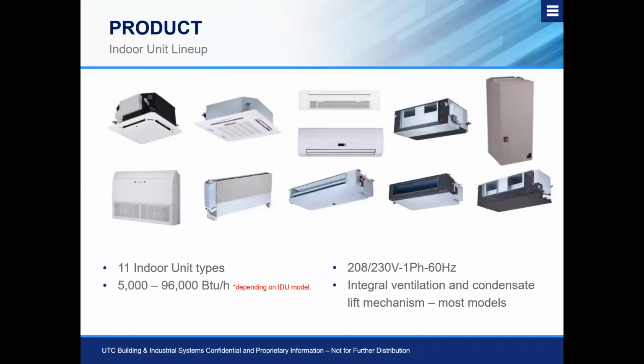All right, so let's switch over to our indoor unit lineups. So with the two pipe range of Carrier products, we have our cassette style units. If we work from left to right, top to bottom, we have our compact cassette, which is on our far left. That is a 2x2 design. To the right of that, we have our 3x3 cassette style unit. Now, of course, the compact is going to be limited on capacity because of the physical size of it, while the 3x3 cassette is going to have more available capacity because it's a larger physical construction, which we can get a large coil.